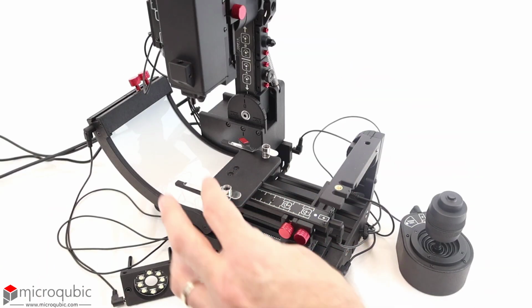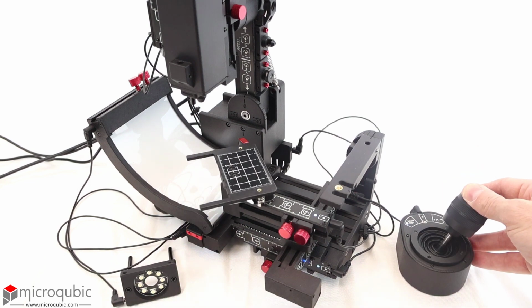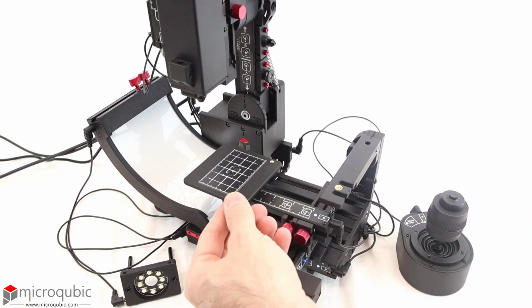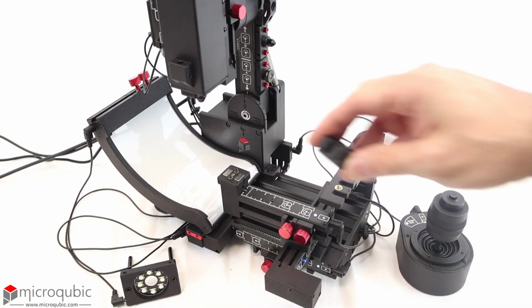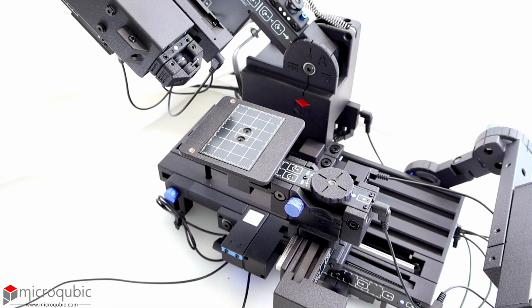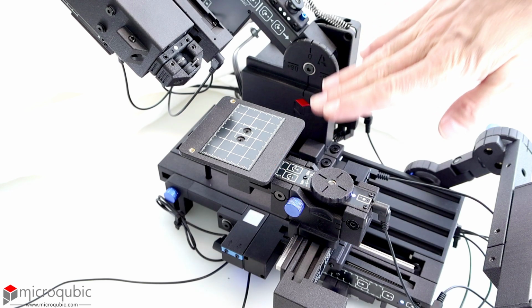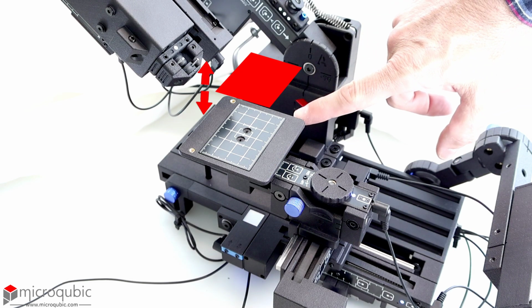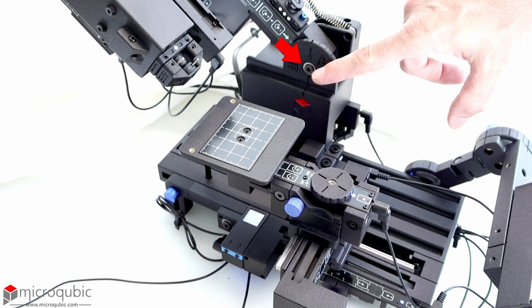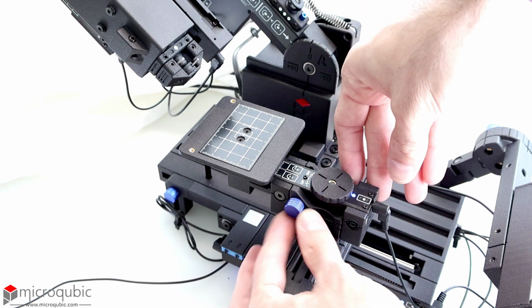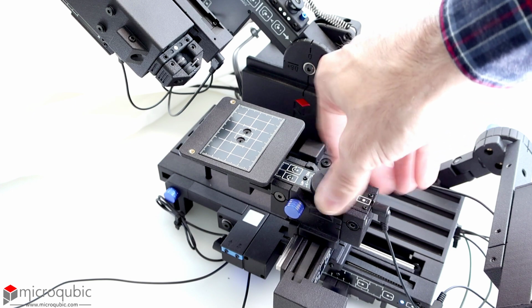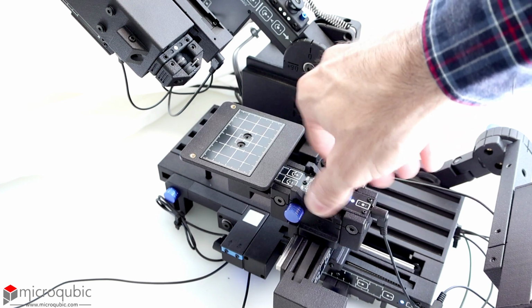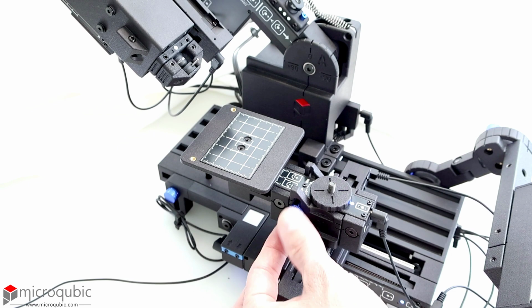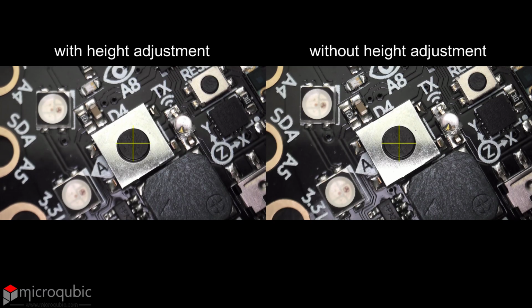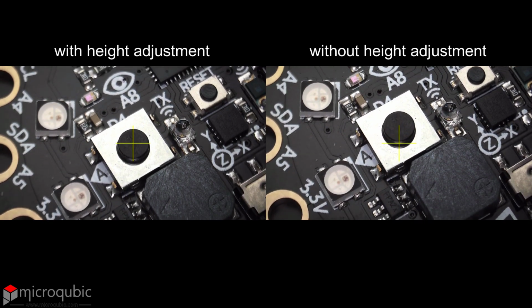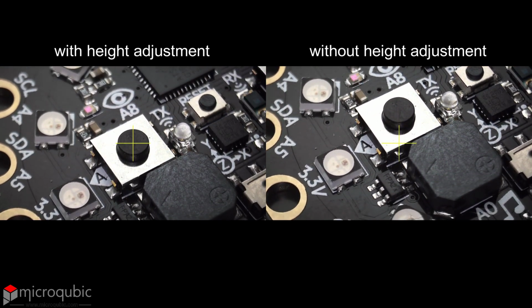The system is provided with multiple sample chucks with integrated magnets. Both sides of the chucks can be used. The newer versions also feature a mechanism to adjust sample height. This helps align the sample's image plane with the primary tilting axis and is especially useful for keeping the point of interest centered when imaging samples thicker than several millimeters. If your microscope does not have this feature, you can still center the point of interest by using the secondary tilting axis.